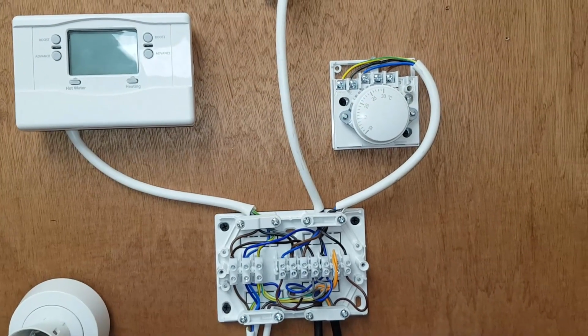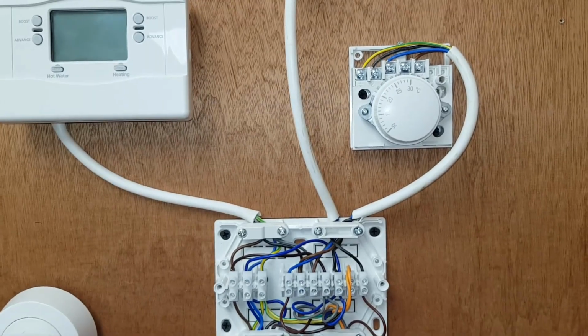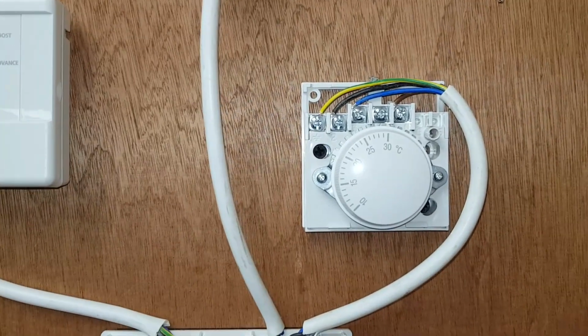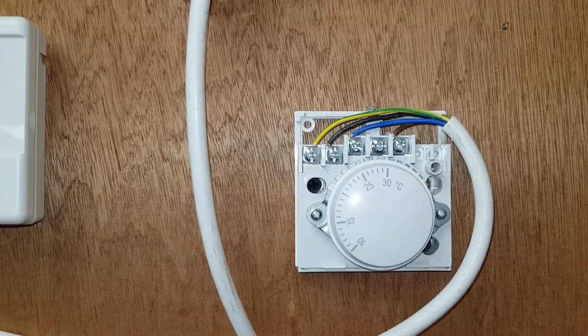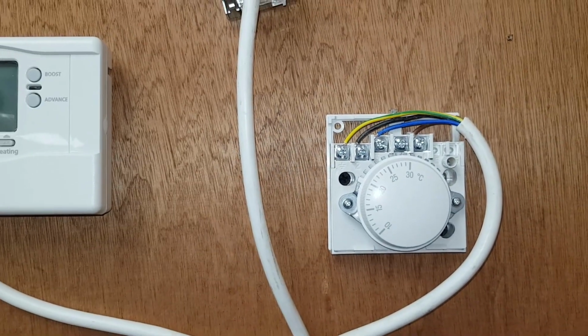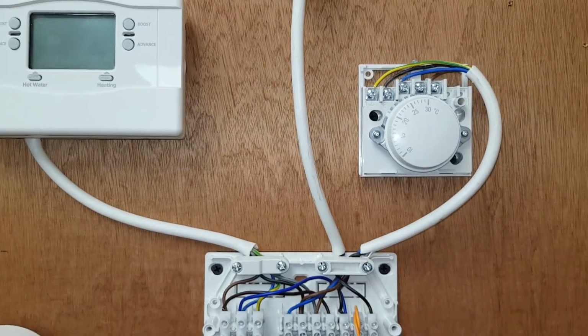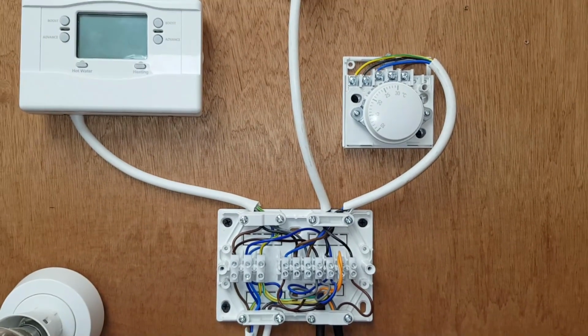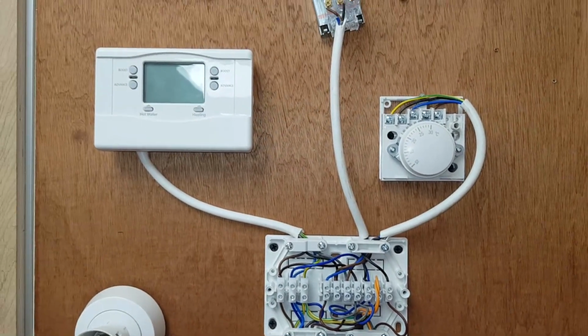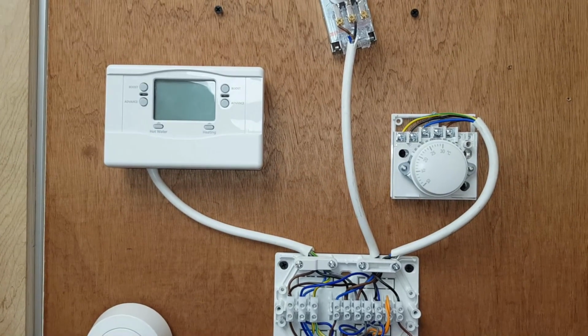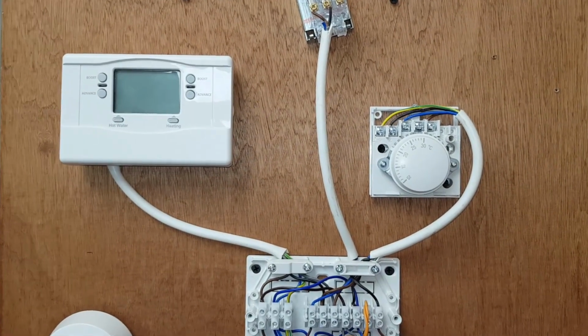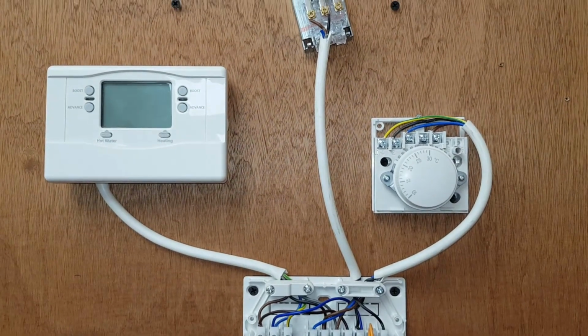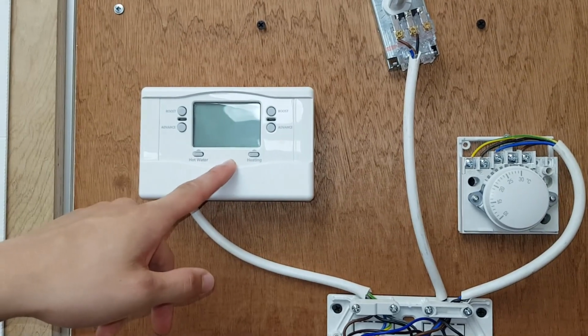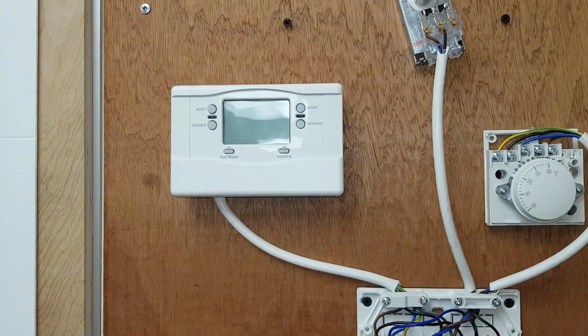All right, excellent. Well done. What would happen if, like you said, you link these two together, 3 and 1, and the pump and boiler didn't come on after doing that? What would you do? What would you be thinking? If you've used a test of linking them out, then there's still no power, then you'll be looking at your programmer failing. That's it. Excellent.